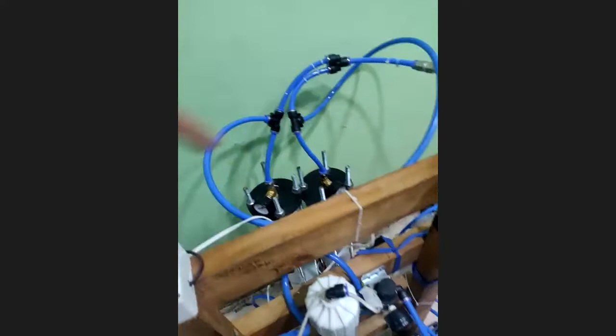Then we have these solenoids, and then it goes inside these canisters. We have removed the equalization valve because during the timing permutation combinations, we saw that it wasn't efficient at all. We have the orifices, 1.5 mm internal diameter, 7 mm, similar to oxygen specification. This is the NRV, and this is the surge tank, about 800 ml. And then we have the flow meter here, and then we get the output.